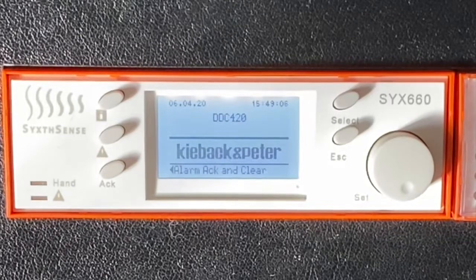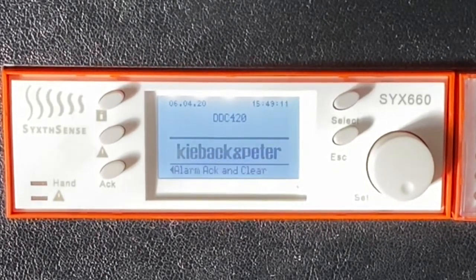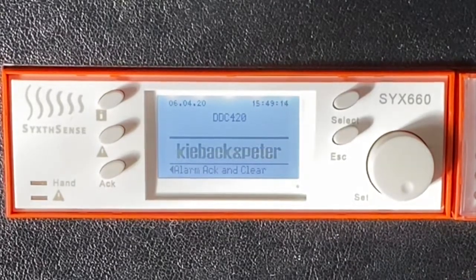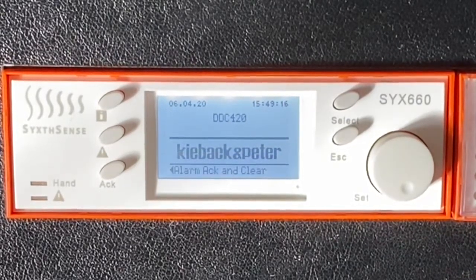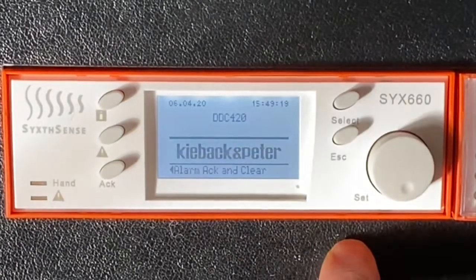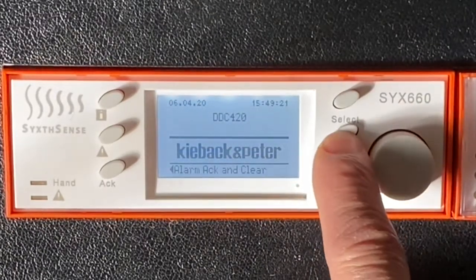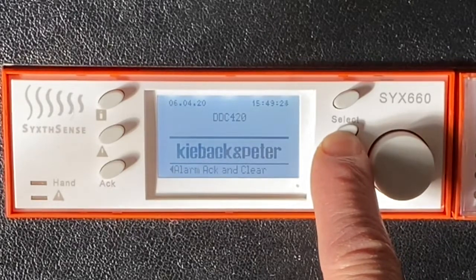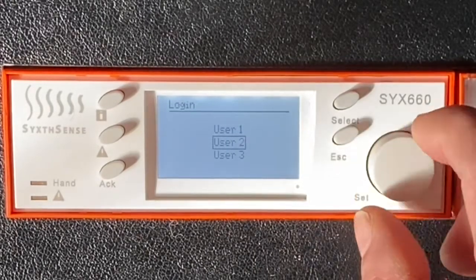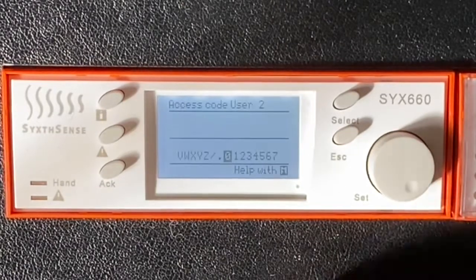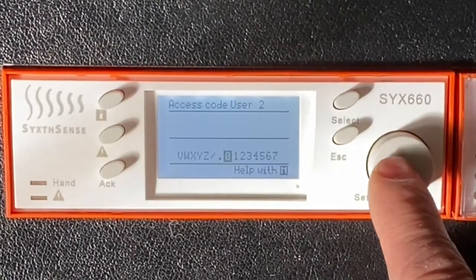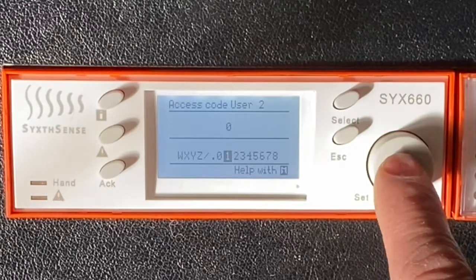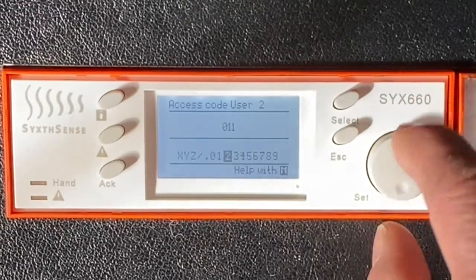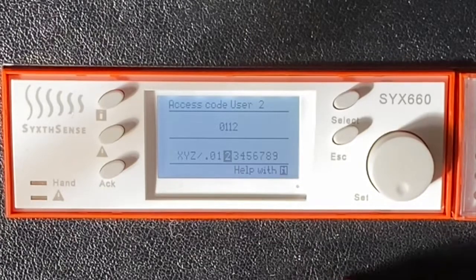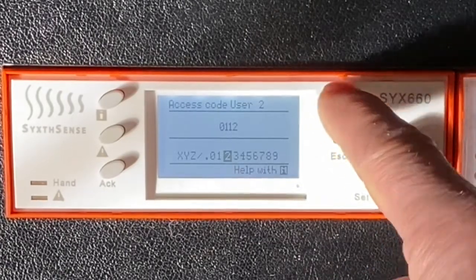First of all, we make sure the controller is correctly installed and powered with all the relevant inputs connected. Once the controller's set up with power, we need to log in at user 2. To do that, we hold the escape key in for 5 seconds, choose user 2 by turning the wheel and pressing the button, and then enter the code 0, turn the wheel once to 1, 1, 2, and press the select button to enter that code.